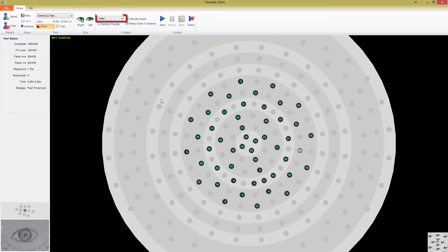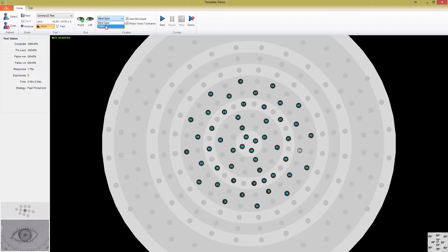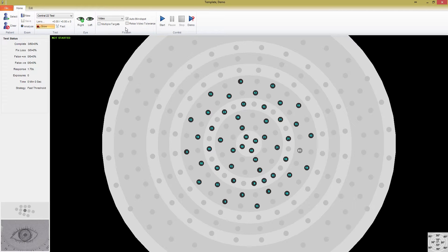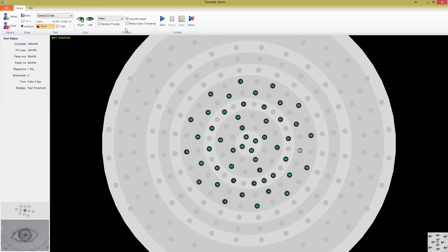If you click on the fixation dropdown menu, you also have the option to move to video fixation. This will speed up your test by removing the need to test the blind spot and reducing the number of exposures in the test. It can also ensure a better quality test, as fixation is continuously monitored, and points that are exposed during a blink or loss of fixation will be retested. For patients that have a hard time maintaining fixation, you can select Relaxed Video Tolerance, which allows for slightly more leeway in eye movement, but also may reduce the reliability of the test. Please be aware that to ensure the best results for video fixation monitoring, the patient must wear the supplied eye patch for monocular testing or the headband for binocular testing. These must be worn correctly or they will not function well, with a central black target located above the nose and not higher on the face than just above the eyebrows. You can see pictures of the correct positioning in our M700 quick setup guide, which was included with your M700.